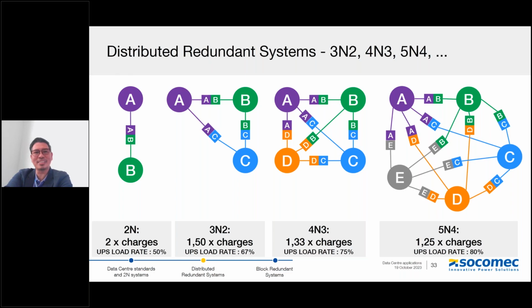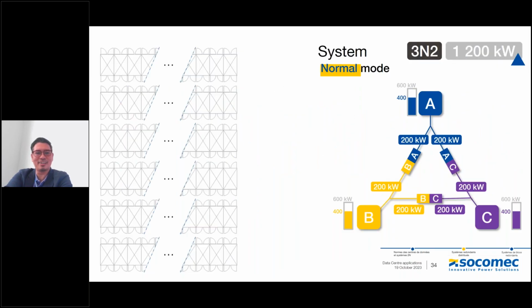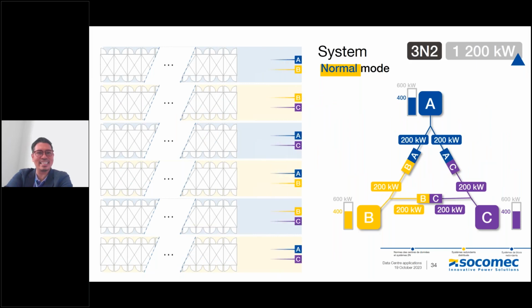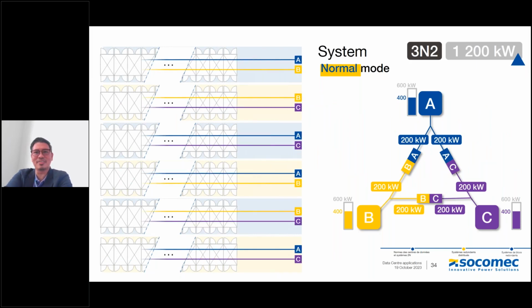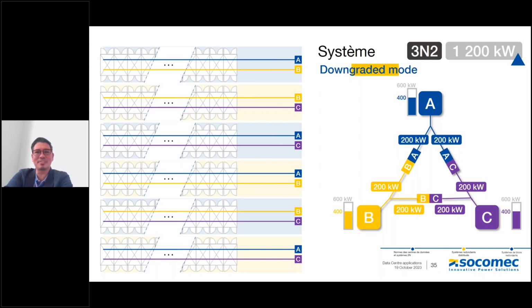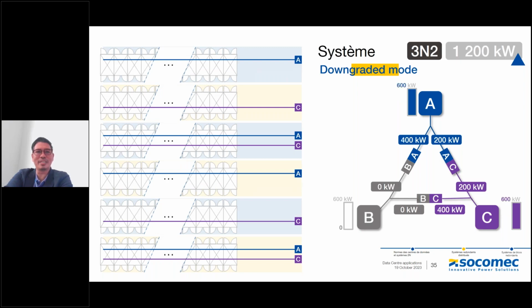Here is a representation, a quick example on how the system works. Everything is in ideal position. We have distributed 3 units of 600 kilowatt, maintaining a load of 400 kilowatt. If any of those systems goes into degraded mode, you will notice that load will be transferred to all the systems. But if it is above here, there will be a possibility of an overload on one of the systems, which can cause a big problem in your installation.